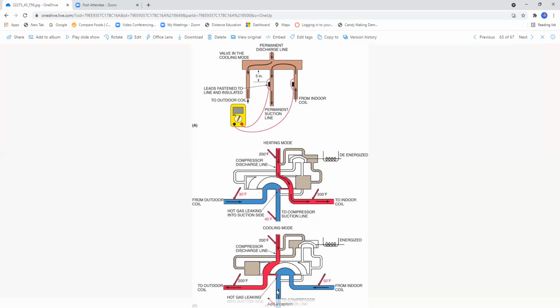Now, in this situation right here, we have the same situation. We have 50 degrees going in here. Notice that we have some refrigerant leaking in here, and same scenario. So in the cooling mode, we're showing a decrease in performance of the indoor coil because we have an internal leak to the reversing valve. The only way you're going to find this out, folks, is you got to do temperature comparison checks. That's the only way you're going to find out.